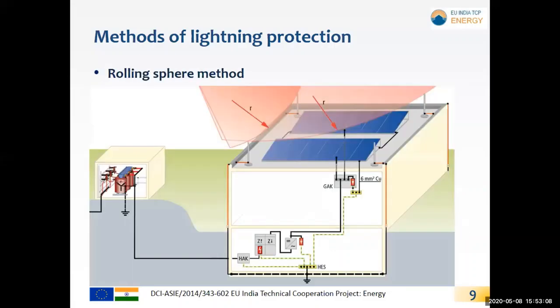The second method is the rolling sphere method. In this method we consider one imaginary sphere, whose radius depends on the intensity of the lightning. Using this, we calculate the height of the rod and the distance between two rods—this is one lightning arrestor, and this is another, and we calculate the height and distance between them.